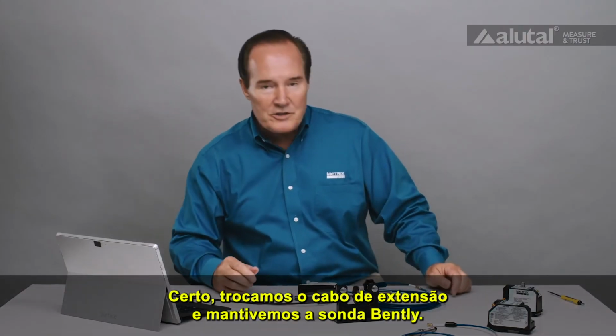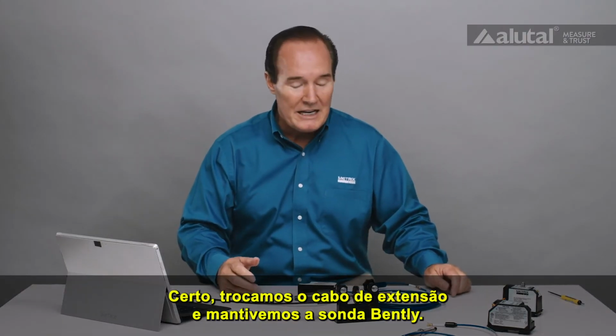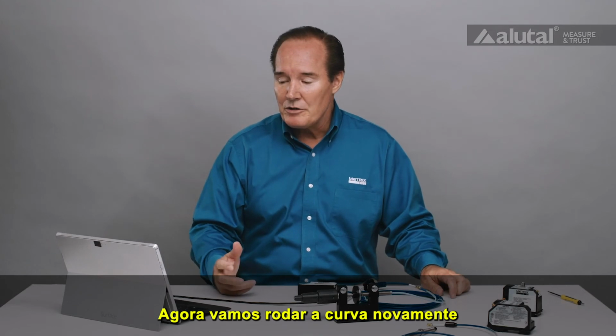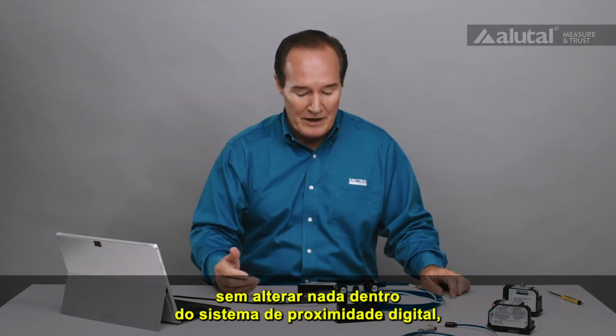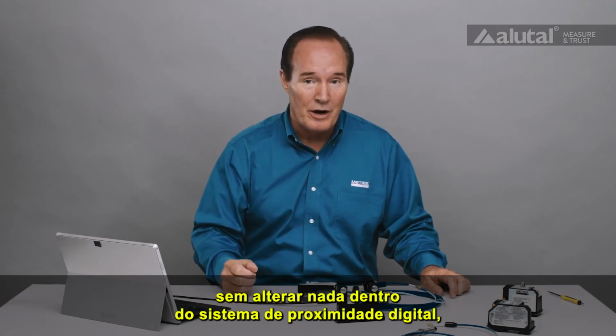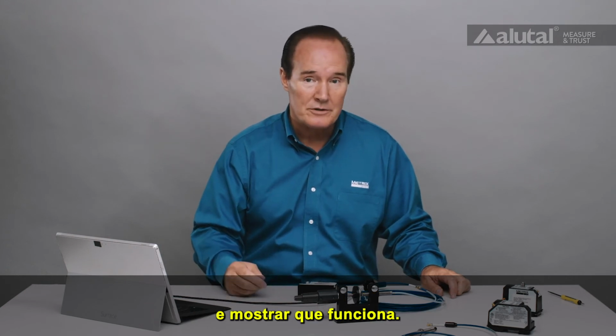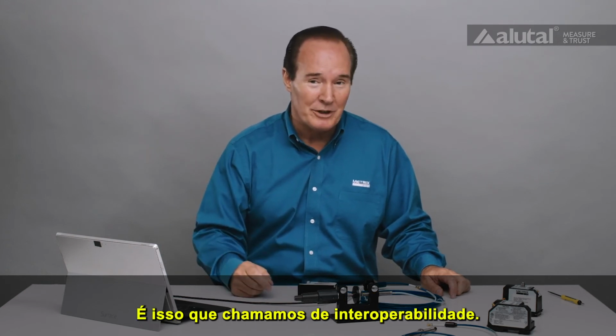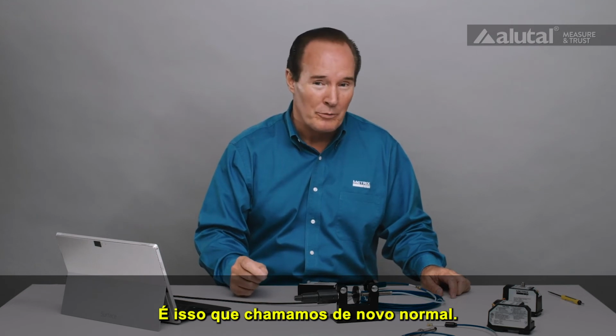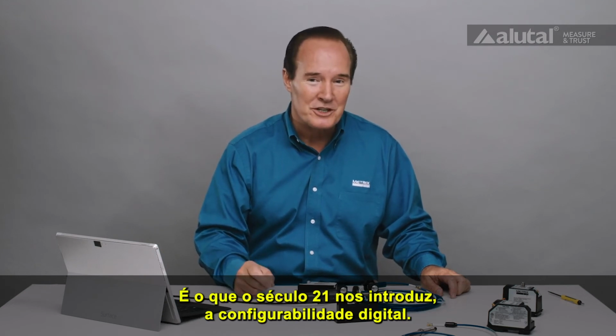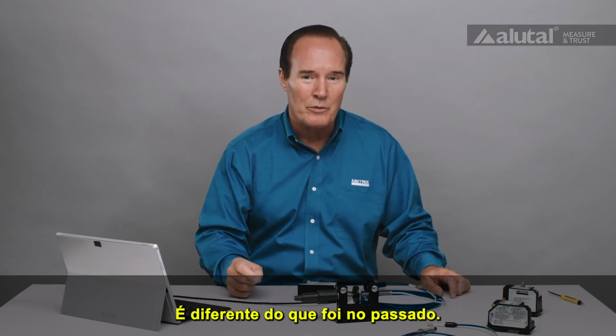All right, so what we've done is we've changed out the extension cable and maintained the Bently probe. Now what we're going to do is run this curve over again without changing anything inside the digital proximity system and show you that it works. That's what we call interchangeability. That's what we call the new normal. That's what the 21st century brings us, is digital configurability. It's different than the way it was in the past.